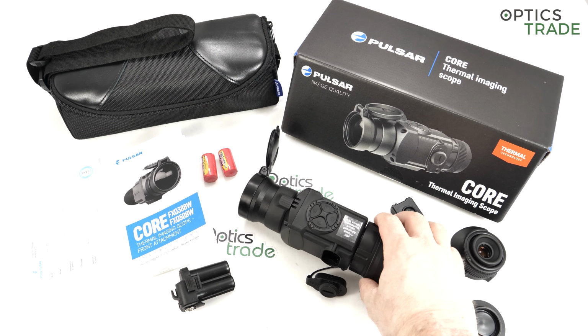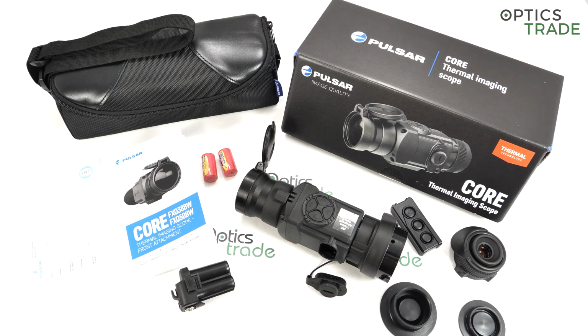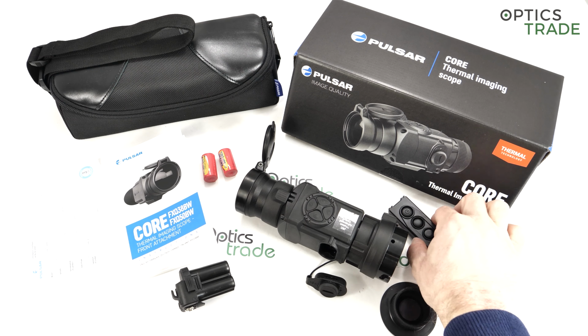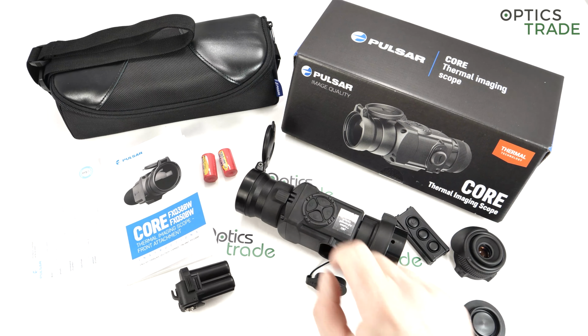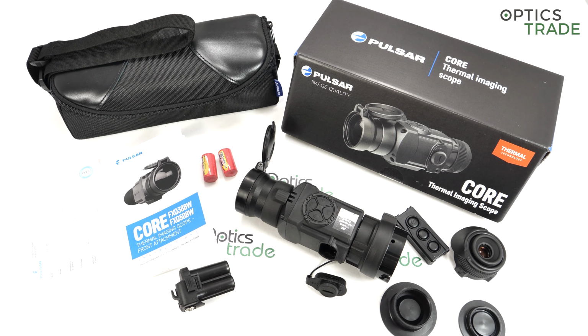And you're able to set this device in 3 different modes. In automatic, where recalibration is done automatically every 30 seconds or something like that. Manually, when you do the calibration only when you wish, with a press of the button on the remote or on buttons on top of the device, or semi-automatic.